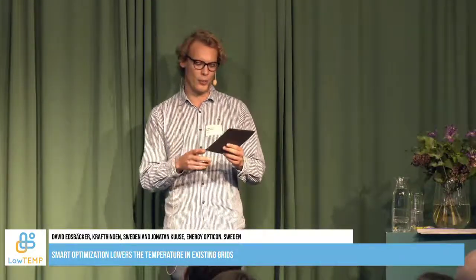Feedback from the grid, which David mentioned before, is important to take both the current status, so we know where we are now. Do we have a network that is hotter than usual, or colder than usual? And that will then help us take the decisions for the future. What should we do from now on? Then these measurements will also be used to improve the model, to adjust the model parameters to better represent reality. And the final point here, which we shouldn't miss out on, is the weather forecast, which in a sense is the base of everything, both forward temperature and the load forecasting.